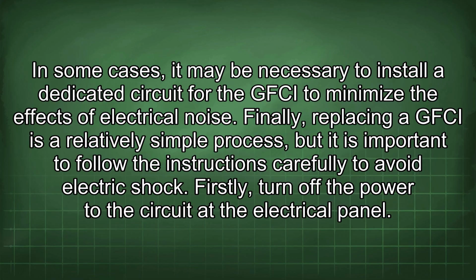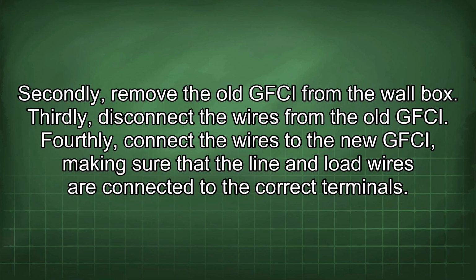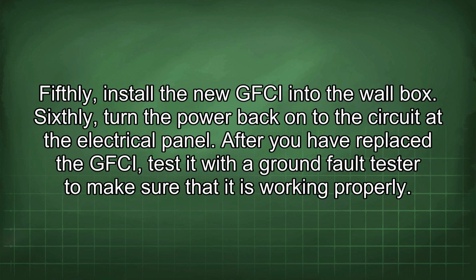electrical noise. Finally, replacing a GFCI is a relatively simple process, but it is important to follow the instructions carefully to avoid electric shock. Firstly, turn off the power to the circuit at the electrical panel. Secondly, remove the old GFCI from the wall box. Thirdly, disconnect the wires from the old GFCI. Fourthly, connect the wires to the new GFCI, making sure that the line and load wires are connected to the correct terminals. Fifthly, install the new GFCI into the wall box. Sixthly, turn the power back onto the circuit at the electrical panel.